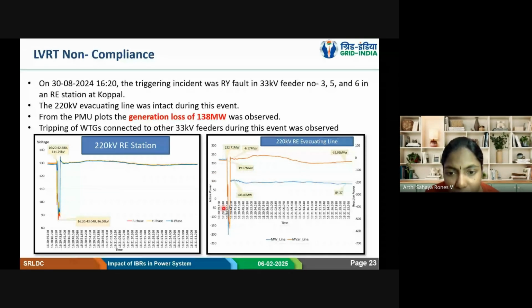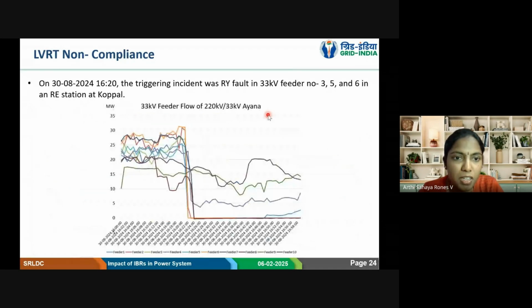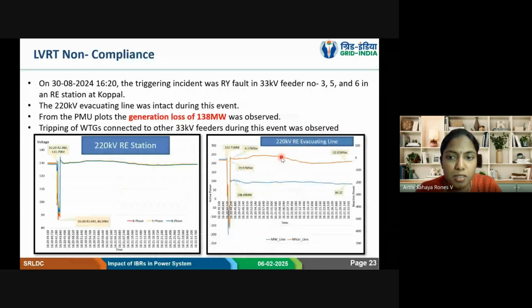During the fault, as per the regulation, active power can go down because reactive power is given preference. But once the fault is recovered, within 1 second, 90% of the pre-fault megawatt should be recovered. These are the grid compliance regulation requirements, but it didn't happen. So in this case, there was a loss of 138 megawatt. So this is one case of LVRT non-compliance. We have checked the feeder-wise flow also, this is from the SCADA. So like this, some LVRT related issues we have observed.